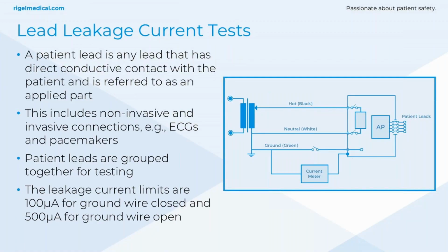So we've got lead leakage current tests. Now a patient lead is any lead that has direct conductive contact with the patient and is referred to as an applied part. This comes from the ANSI ES 60601-1, and it includes non-invasive and invasive patient connections. So anything that comes in contact with the patient, including ECGs, pacemakers, defibrillator paddles, anything that's specified on the medical device as an applied part. When it comes to patient connections, they have lower leakage limits of 100 microamps to reflect the hazards.